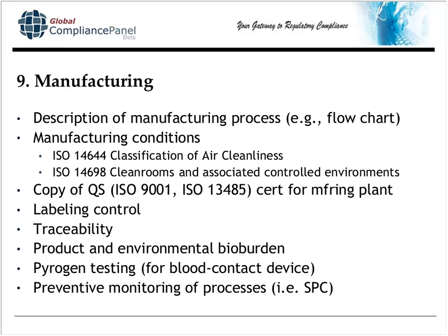Section 9, manufacturing, asks you to describe your manufacturing process. Most companies just make a flow chart. If either of the manufacturing conditions 14644 or 14698 apply to you, you've got to show compliance with those standards. If you manufacture at a different location from where you manage, you've got to have a copy of the quality system cert for that manufacturing plant. Explain your labeling control processes and traceability processes in this section. Any bioburden determination, pyrogen testing for direct blood contact devices, and any SPC monitoring you perform are referenced in this section as well.